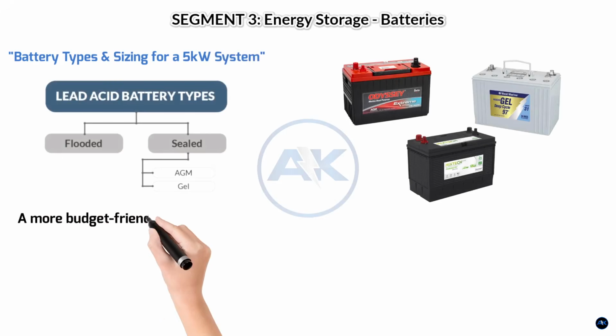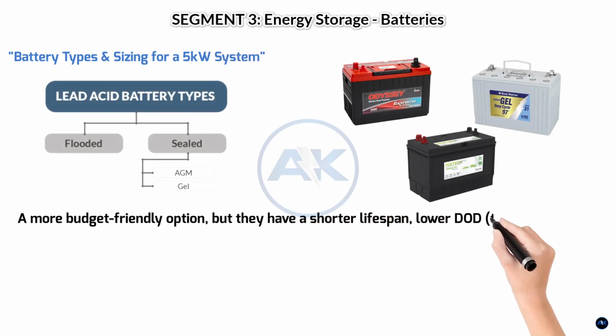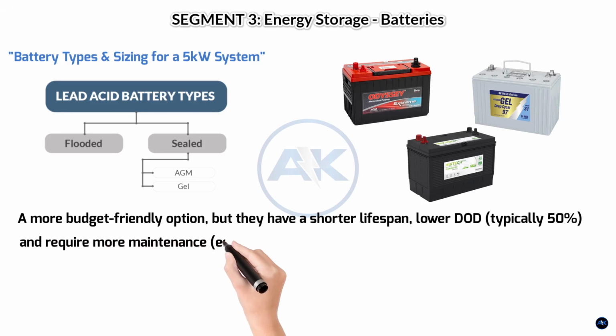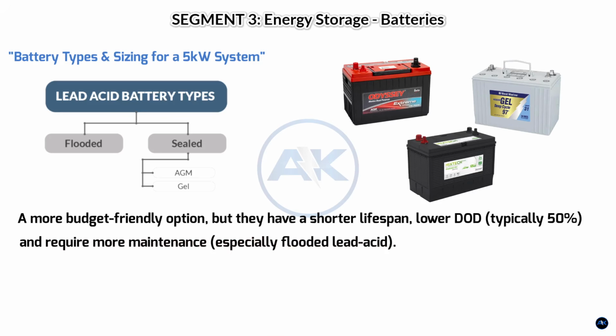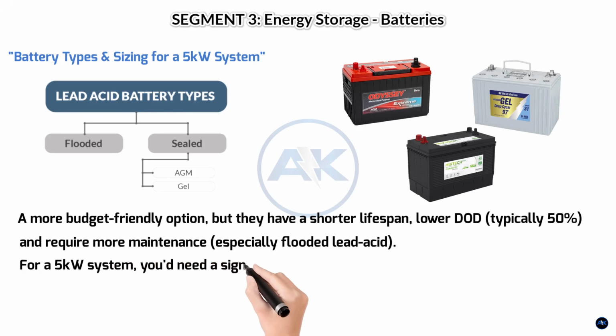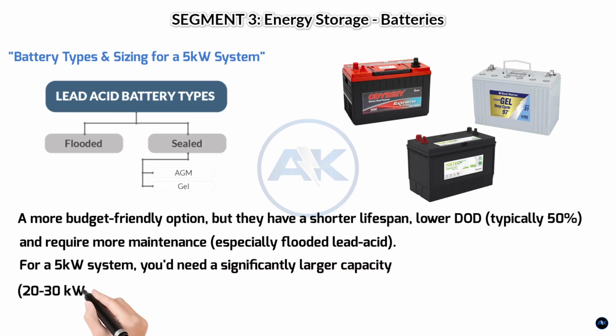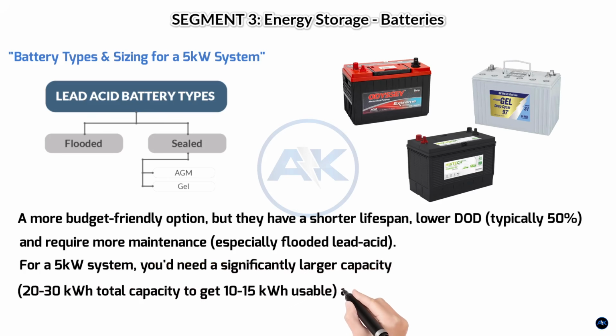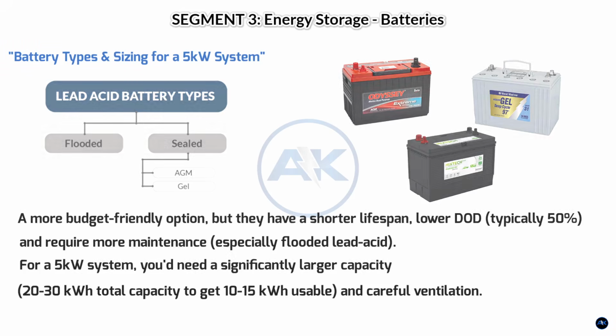Lead acid: gel, AGM, flooded. A more budget-friendly option, but they have a shorter lifespan, lower DOD, typically 50%, and require more maintenance, especially flooded lead acid. For a 5 kilowatt system, you'd need a significantly larger capacity, 20 to 30 kilowatt hours total capacity to get 10 to 15 kilowatt hours usable, and careful ventilation.